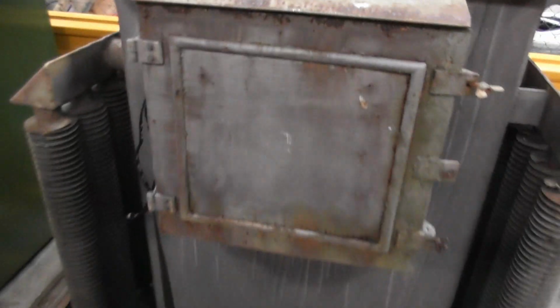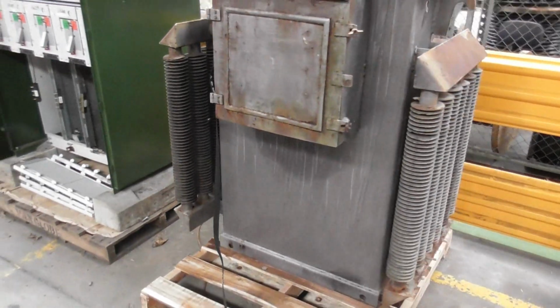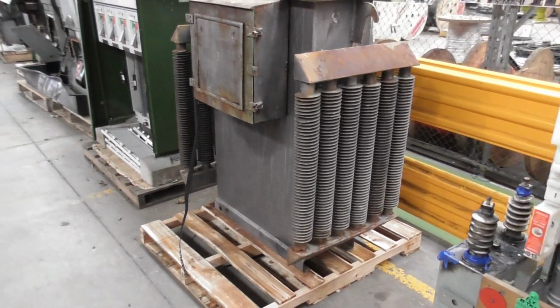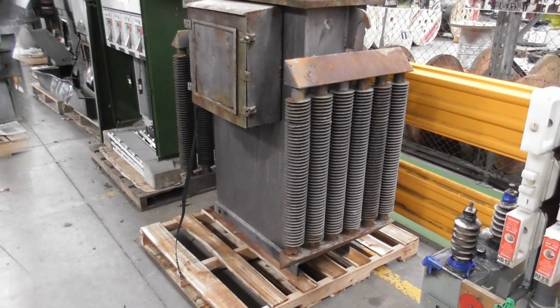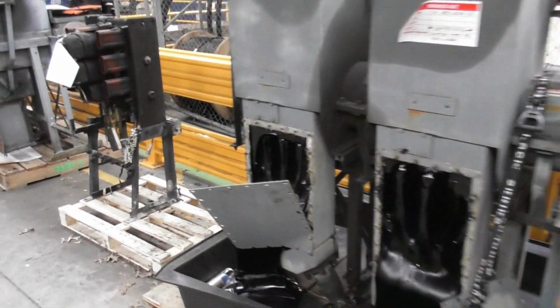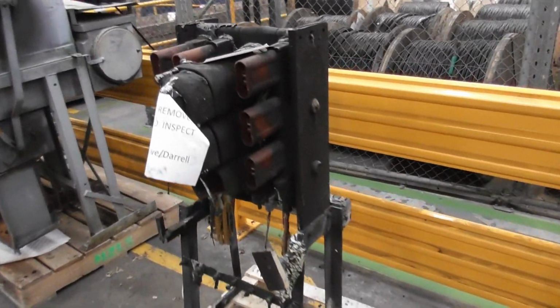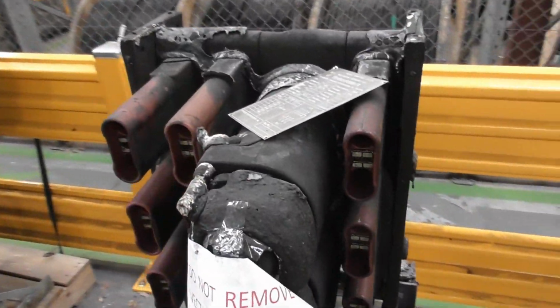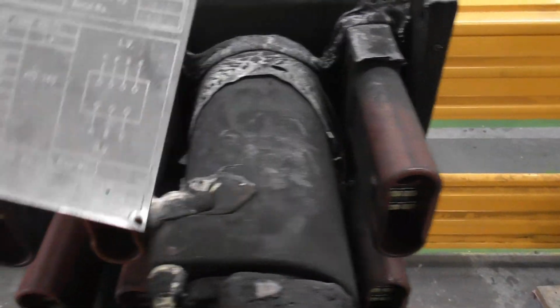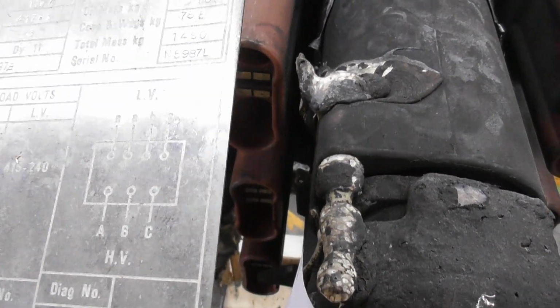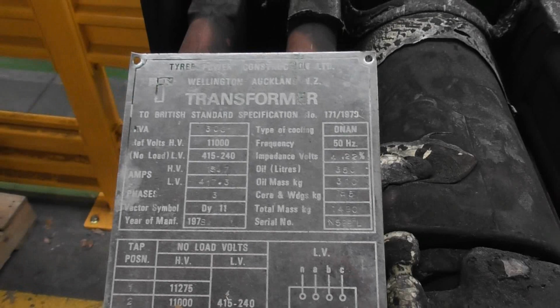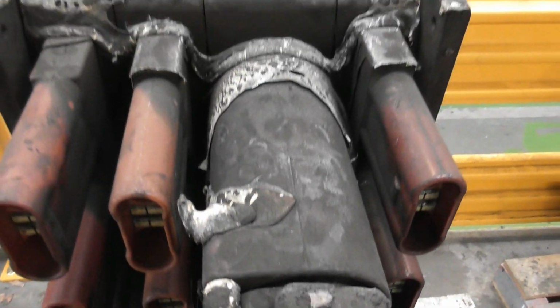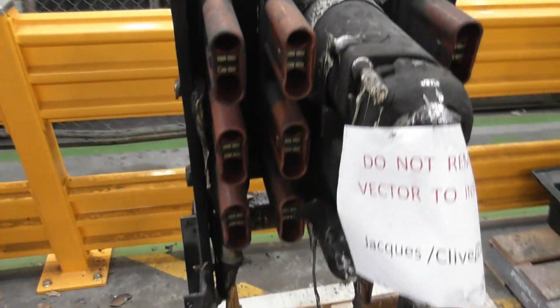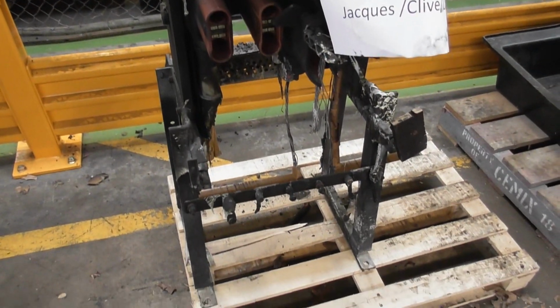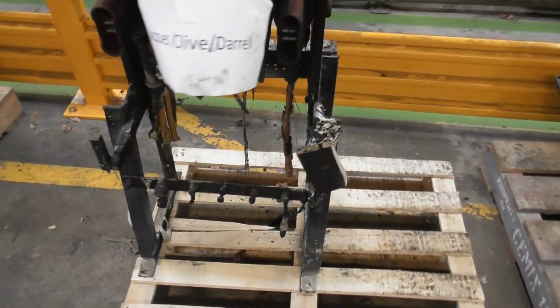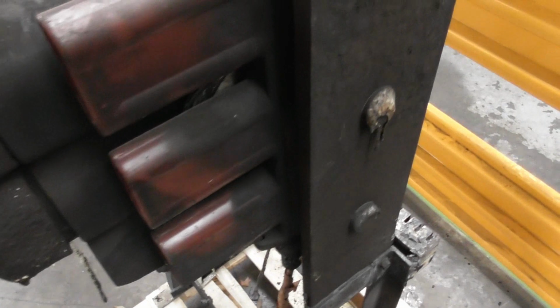So all by itself it's quite a cool transformer. Not sure where it came from, but it's been around for many years. Old Long and Crawford stuff, and this is an old Hazemeyer unit. Oh, nameplate. Nameplate from a 500 kVA. This is blown up. Cable failed, and it's carbonized itself.